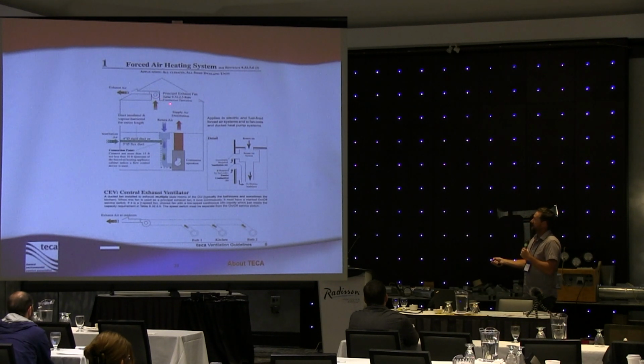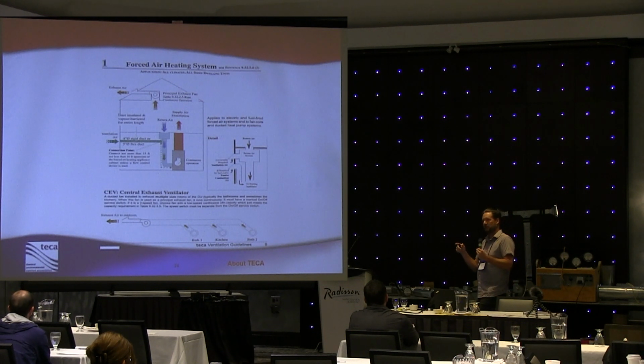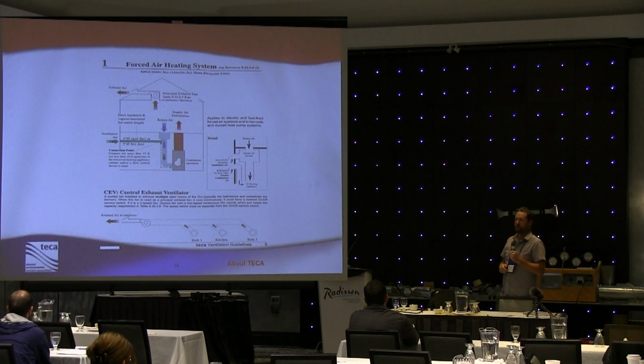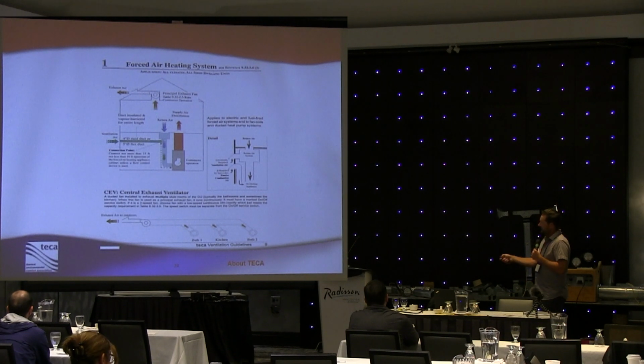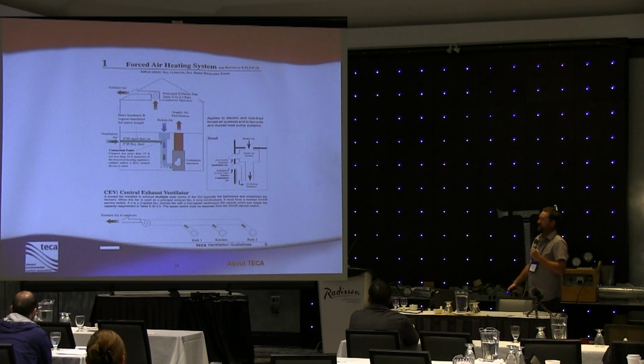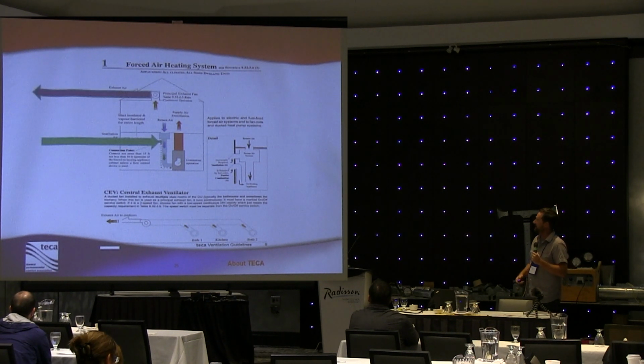So what we do here is there are some fans available that will run on multiple speeds, but what we want to make sure is that when it's running on this low speed continually, it meets the prescribed ventilation rate, which you will find in the BCBC, and you'll also find that code table in our manual. So simply enough, we've got all of our stale air exhausting out through one bathroom exhaust fan, and we're bringing fresh air in from the outside, just passively, connected to our return air ductwork for our forced air heating system. And it looks something like this.